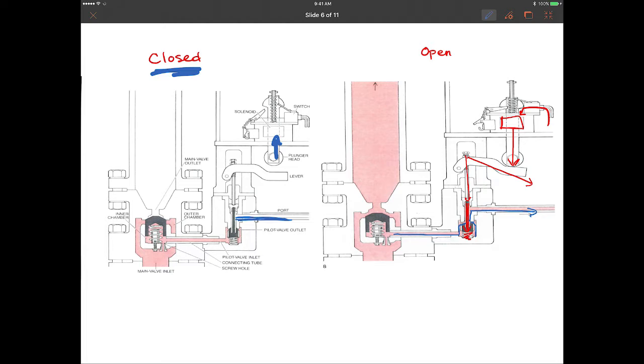Okay. So how does this relate to what the operator saw in the control room that day? Well, the interesting thing is when this solenoid over here is actuated, or energized, a signal is also sent to the control room to light up the PORV indicator. And so that light in the control room lights up and says to the control room operators, hey guys, PORV is open. Now that's interesting. There's a fine line here, because what it's really saying is not that the PORV is open, it's just saying that the solenoid is activated. But the operators were trained and understood the system to work such that when they saw the light being turned on, they understood the PORV to be open.